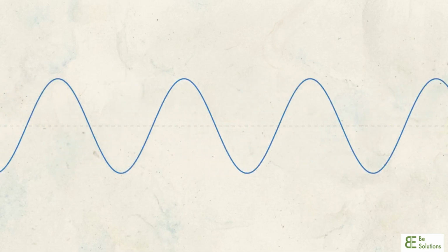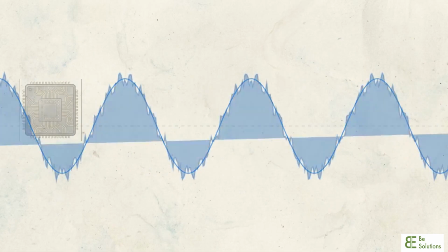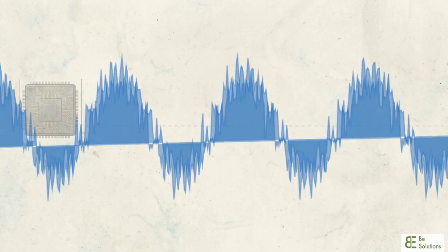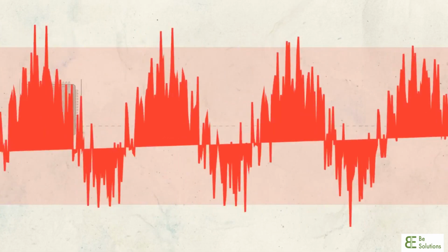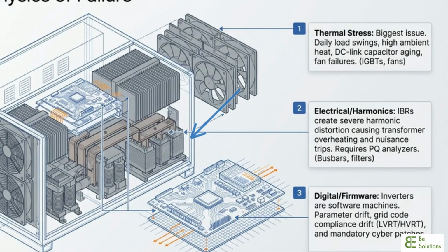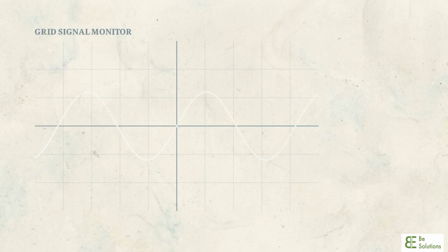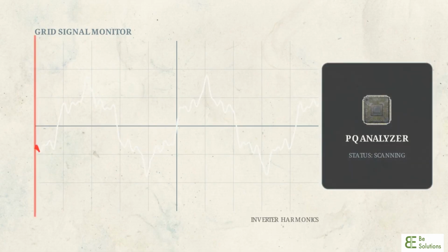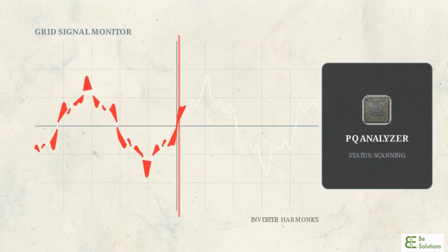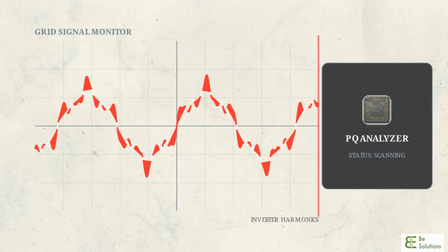Next is the electrical threat. The high-frequency switching inside these inverters generates severe harmonic distortion. If left unchecked, these aberrant frequencies overheat nearby transformers and trigger protective relays, resulting in unexpected plant shutdowns, known as nuisance trips. To protect the hardware, operators install power quality analyzers to continuously monitor the grid's waveforms and detect the specific frequencies of the distortion.